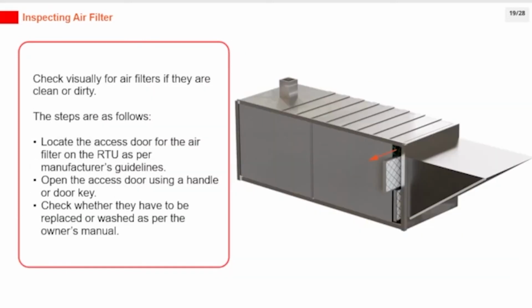Check visually if the air filters are clean or dirty. The steps are as follows: locate the access door for the air filter on the RTU, as per manufacturer's guidelines. Open the access door using a handle or door key. Check whether they have to be replaced or washed as per the owner's manual.